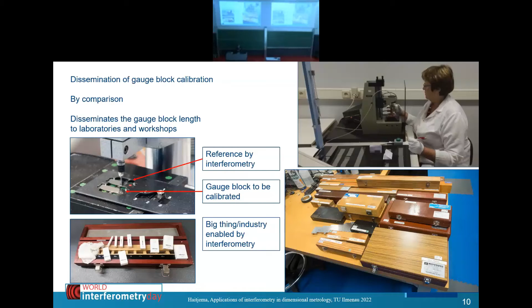Then a question: what can you do more with a gauge block interferometer? Then I thought, I saw something about ball measurements this morning in the schedule. I once thought, okay, what can we do more with a gauge block interferometer than just measurement of gauge blocks? Well, what you can also do is measure balls. If the ball is small enough, it will just fit under the gauge block. And then you need some piezos to make the gauge block exactly parallel to the flat. And then you have this optical scheme, and then you can measure the ball as if it is a gauge block, just with a bit larger length due to the ball.